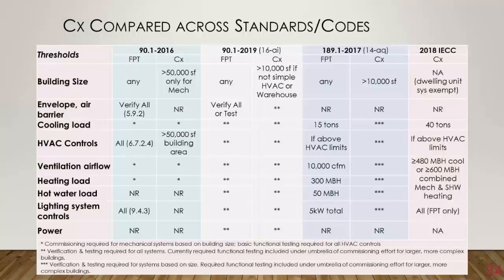And frankly, IECC, I would say, came ahead of both 189 and 90.1 as far as putting in a somewhat detailed requirement for commissioning documentation requirements. Although the commissioning in IECC is pretty much limited to the mechanical and service water heat systems. Lighting, there's the same functional performance test in 90.1 for lighting controls, but it's not rolled under the commissioning envelope as it is in 90.1. So that's a difference we see there.